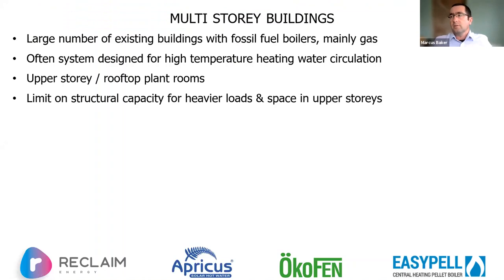So if we just move on to multi-story buildings, I've mentioned that 25 meters is our standard for on-boiler pellet transfer, but there's ways of us managing it in other ways. And obviously there's a lot of multi-story buildings out there, and they often, I think particularly a retrofit, are going to have high plant rooms that maybe haven't necessarily been thought about particularly for decarbonisation at all. And there's a limit on structural capacity up in those upper stories. And we often have high temperature water systems that are set up there. So heat pumps might be challenged by those conditions.